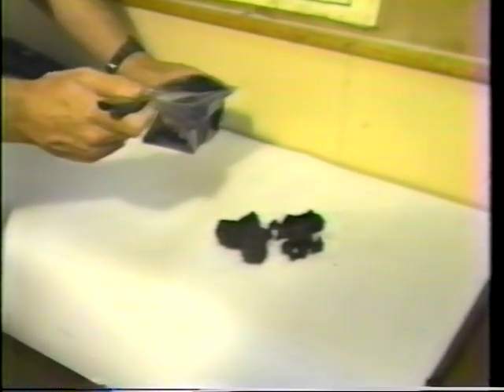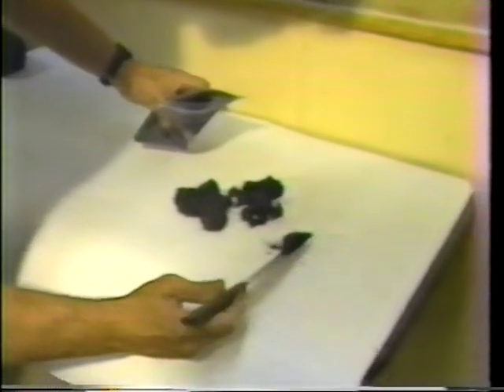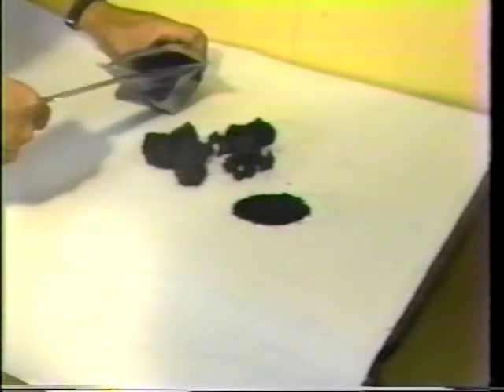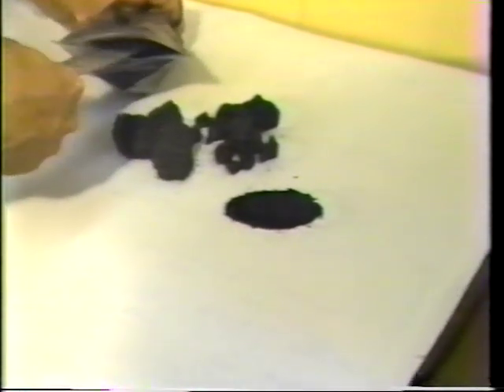Now, what do you have there in your hand? This is a sample of the product coming to the burner from the pulverizer. Put a little more out there. Would you smell? That's what I'm looking for. Now, what is the fineness on this? Okay, the fineness here is 88% minus 325 mesh.